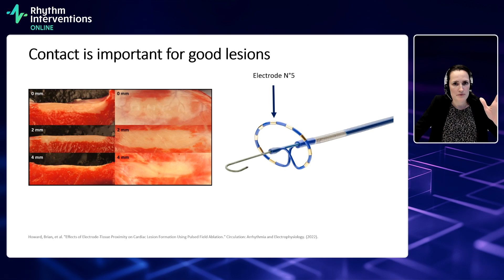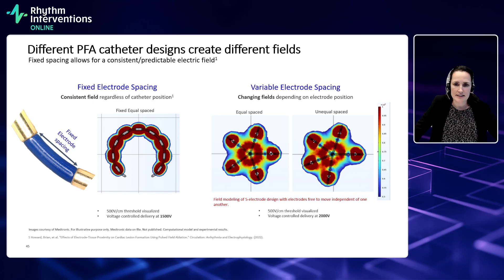The PulseSelect catheter has a fixed electrode spacing. This allows a quite predictable electrical field. Other catheter designs, like the pentaspline catheter, have varying distance between the splines, and this results in a variable electrical field, let's say.